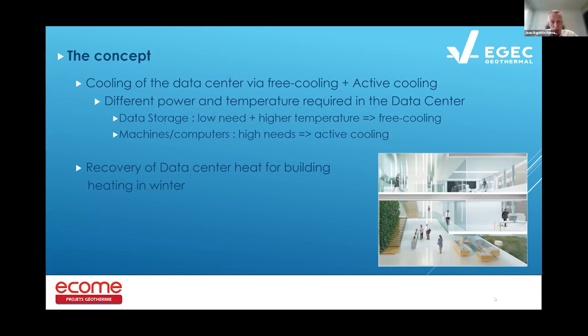In this project, water from the ground is first used to free-cool the storage systems, then it goes to heat pumps which provide lower temperatures to cool the computers. In both cases, it's a geothermal system being used. Part of the energy from the data center is also used to heat the university building. As long as possible, the heat is used for the university, and especially in summertime when there's no heating need, the heat is injected back into the ground.